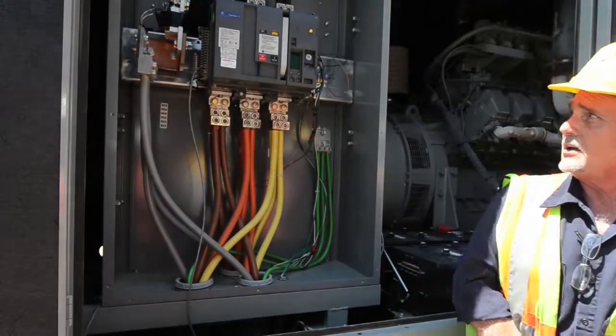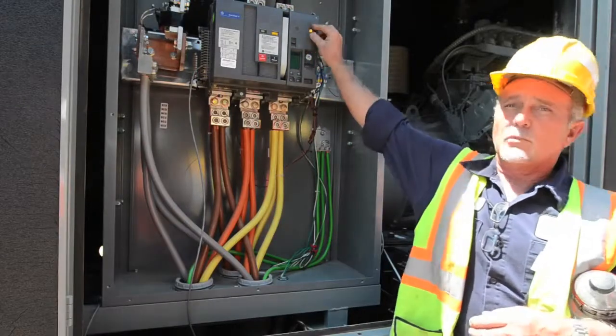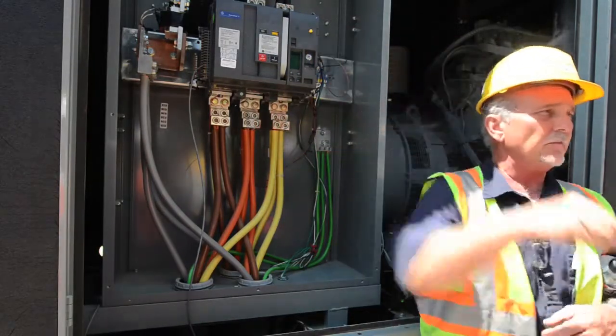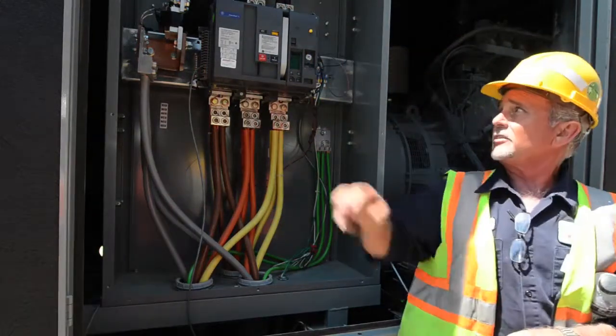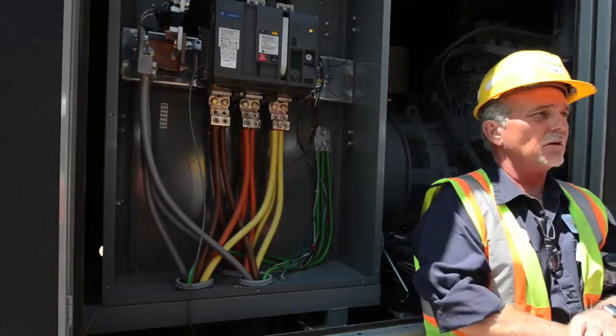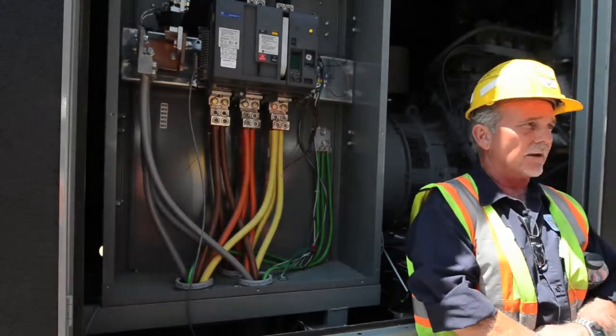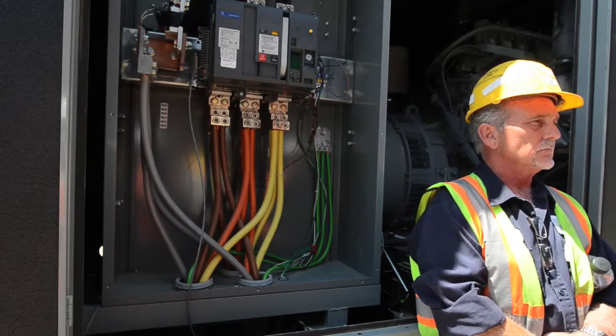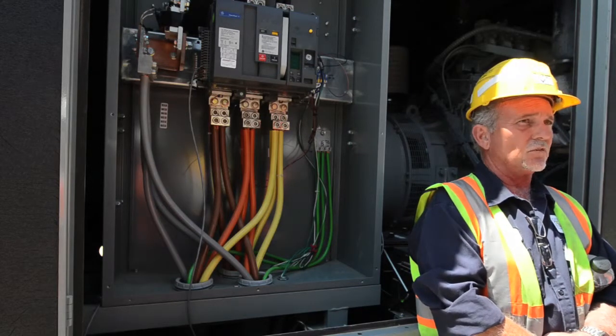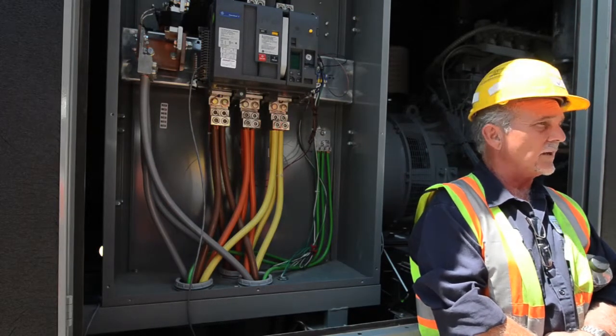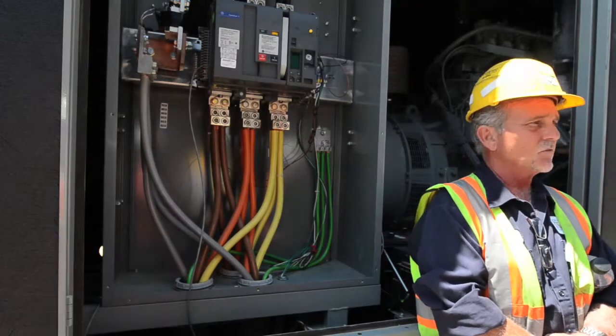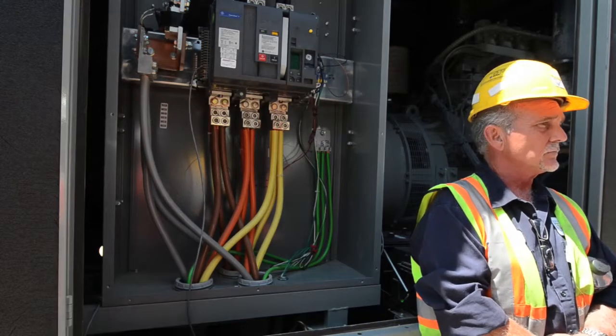So, in the event that it does overload, the bell alarm will pop out, the breaker will open if it's going over current. And yes, at that time, this can be reset and you can make another attempt to put it back in auto and let it go online. But you might want to at that time decide what your current loads are and what's dragging it down, and you may want to shut something off so that you don't overload it again.